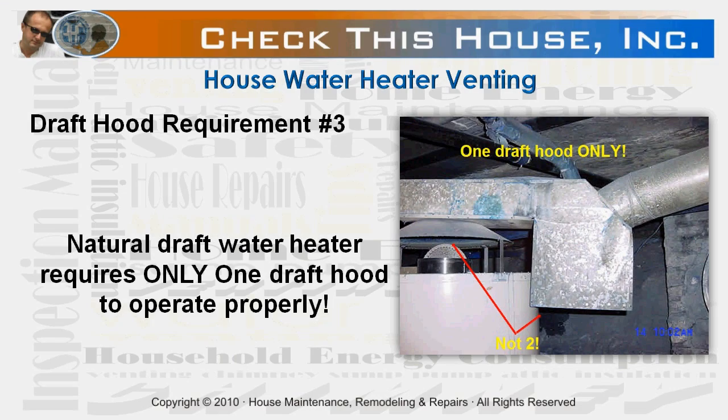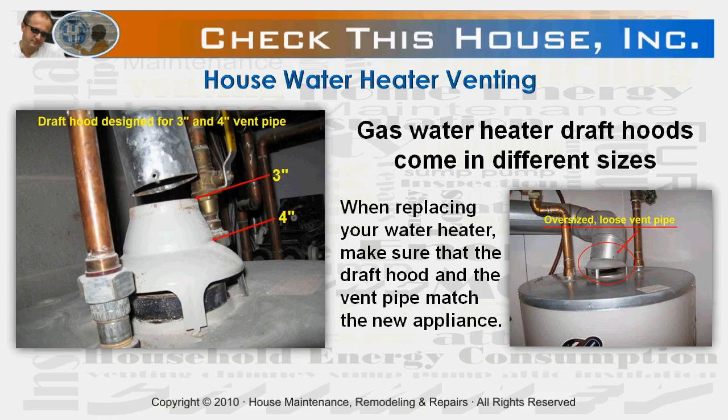Draft hood requirement number three: a natural draft water heater requires only one draft hood to operate properly. As water heater draft hoods come in a few different sizes, it's always best to use the new draft hood that came with your water heater, not the existing one that was attached to the old appliance, even if the new and old one look absolutely the same.